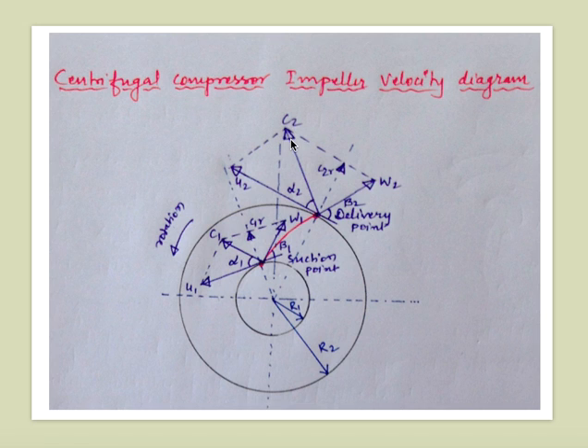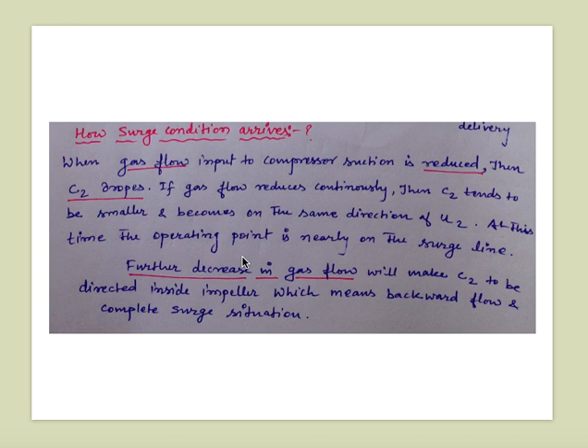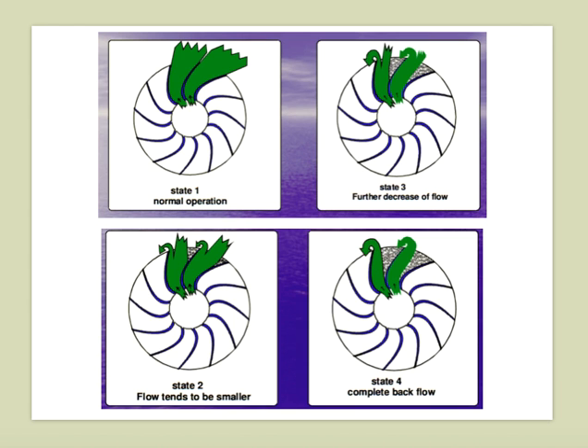If we further reduce gas flow to the compressor suction continuously, c2 tends to become smaller and align in the same direction as u2. The magnitude of the c2 vector keeps reducing — initially it is large, then progressively shorter. At a certain point, drawing the parallelogram shows the resultant c2 becomes almost parallel to u2. This is the initiation of surge condition, and at this moment the operating point is nearly on the surge line. Further decrease in gas flow will cause c2 to be directed inside the impeller, meaning backward flow — complete surge situation.